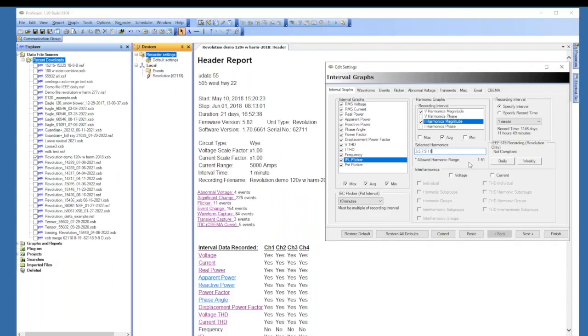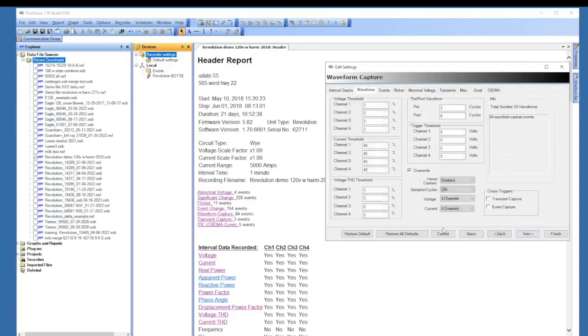Odd harmonics typically are the ones that cause the problems, and so you can type in the odd harmonics with a comma in between. Now on the Revolution, if you are doing IEEE 519 recordings, all you have to do is click on the daily, which gives you a 3-second interval. You'll need to record for at least a couple of days in order to get that daily report. If you click on weekly, you get a 10-minute interval. And those set up this page automatically by clicking on those. If you have enough memory, at least 512 in the Revolution, you can choose the daily and also record for more than 7 days. You can get both the daily and the weekly IEEE reports out of that. So those two pages, the basic and the advanced here, set up all this interval recording. And then the next pages go through and set up these individuals.